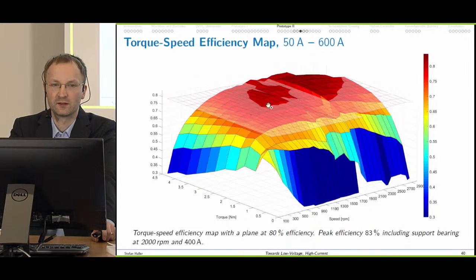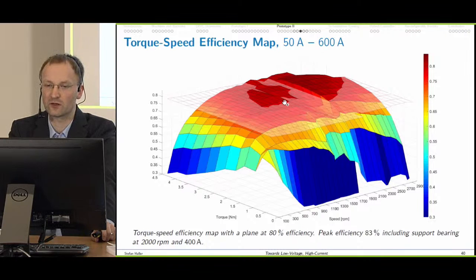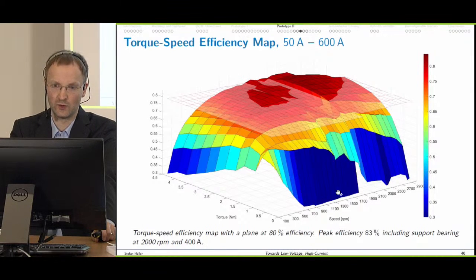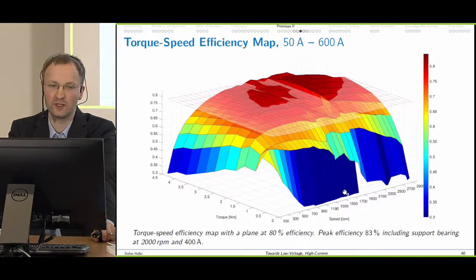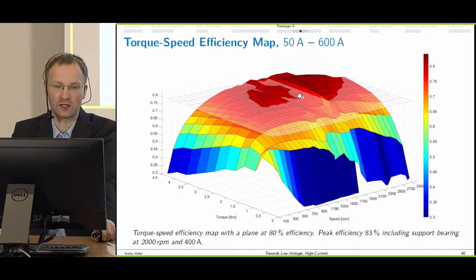What we see here is the torque speed efficiency map of the machine, including the support bearing. Since we didn't have any, let's say, calibration data we trust for the support bearing, we decided to publish all results, including the support bearing. So the real machine's performance was actually a bit better than reported here. So we reached 83% here at that plane, which is at 2000 RPM and 400 ampere.